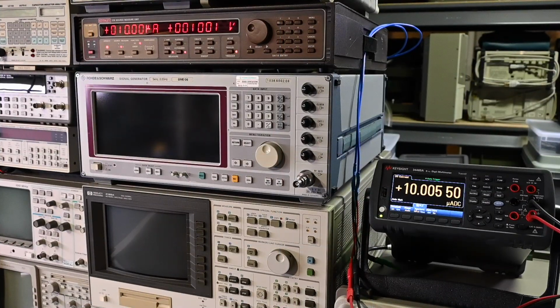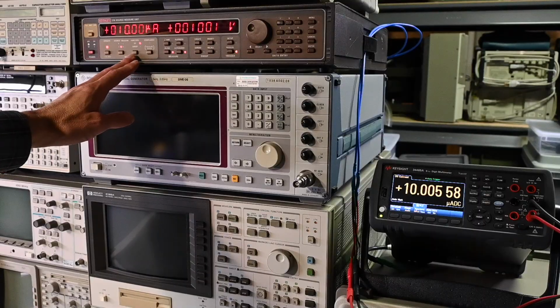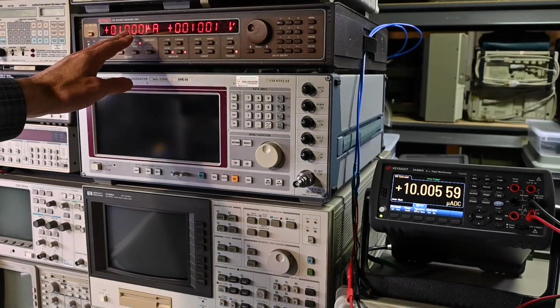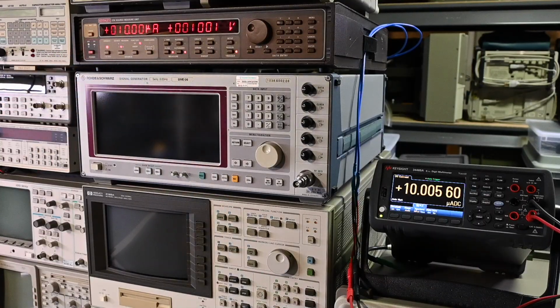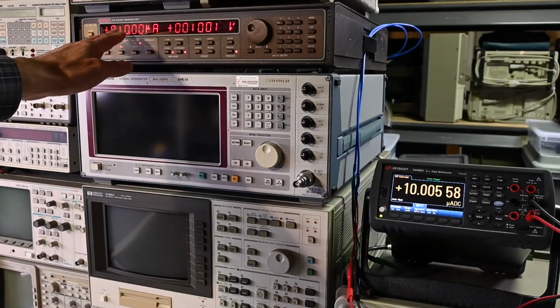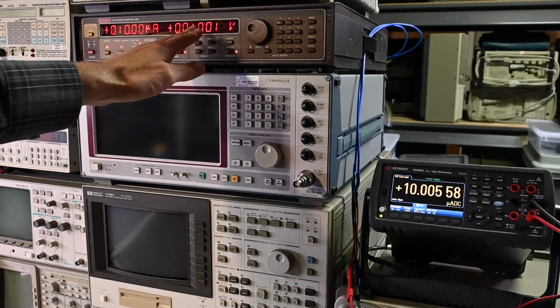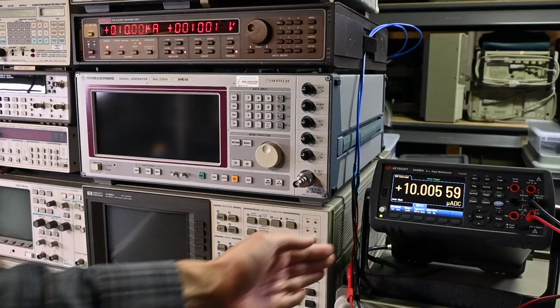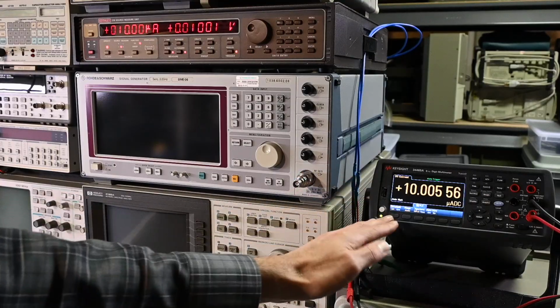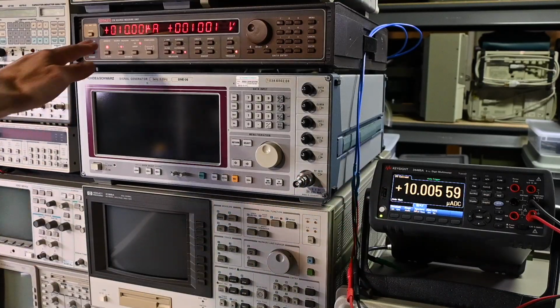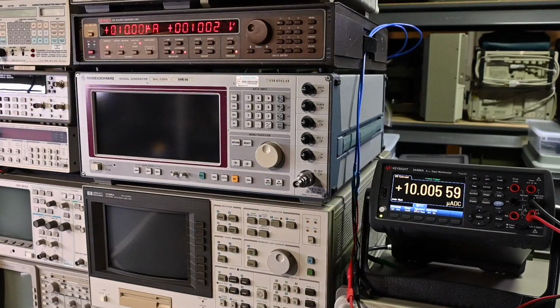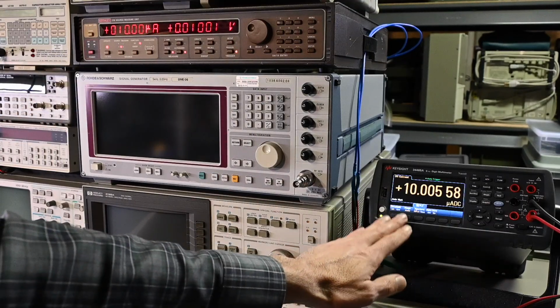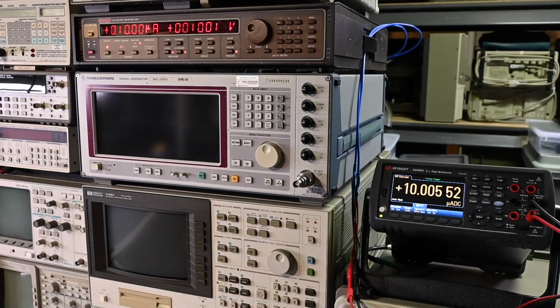Some of you might be asking, how do I know that the Keithley 236 is supplying the current that's indicated right here, when this is an entered value for the current? This is not an actual measured value on this display, whereas this is a measured value for voltage. Well, here's the answer. You can see on the Keysight digital multimeter, it's right at 10 microamps, and over here, 10.00 microamps. So this is exactly in agreement, and this Keysight digital multimeter is under a factory calibration, and it's known to be very, very accurate.